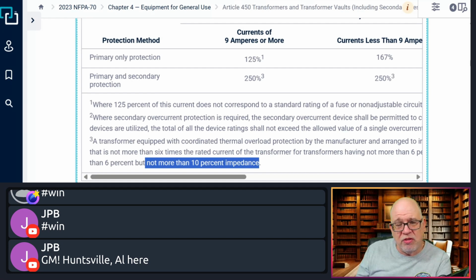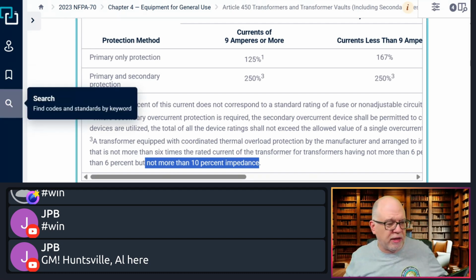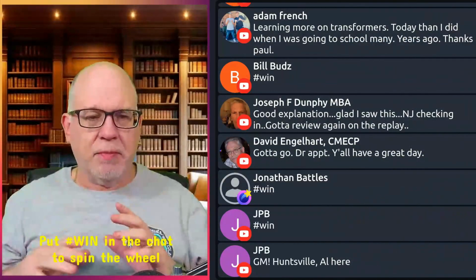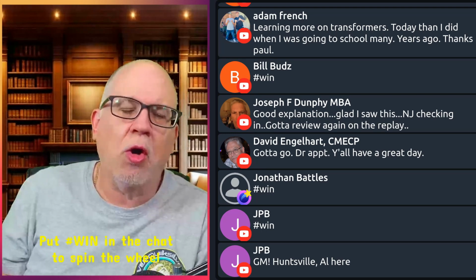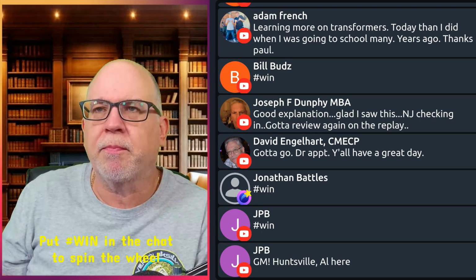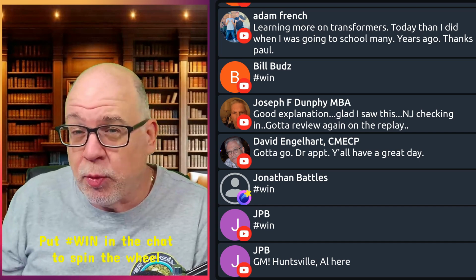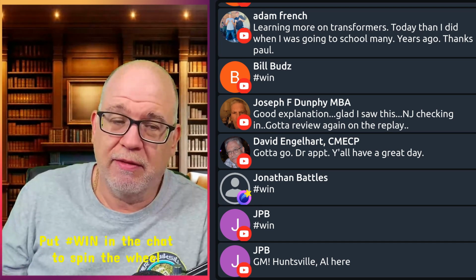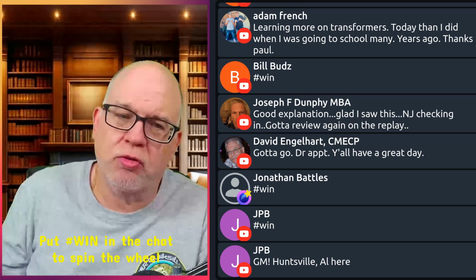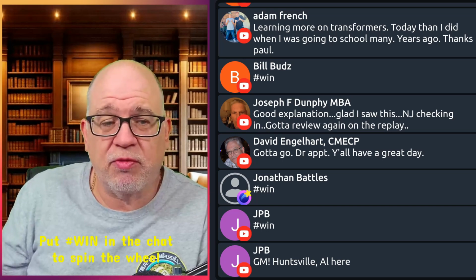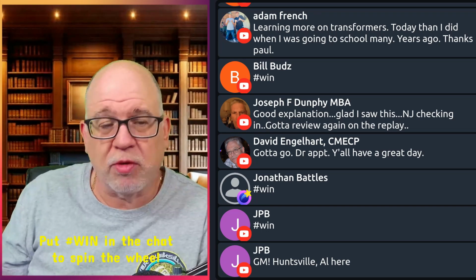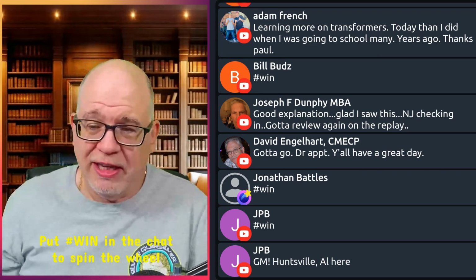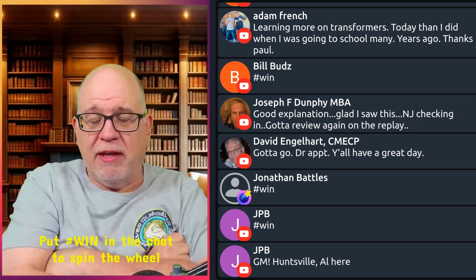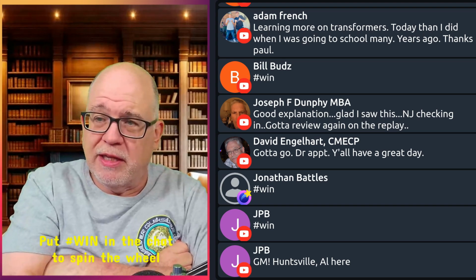So most exams, we just get asked, what's the maximum? If there's a secondary protection, what's the maximum protection on the primary of that transformer? 250%. Now, I'm just talking, but here's something you have to be concerned about and prepared for: if you go up to 250% because you're doing the protection of the transformer, you may not adequately be protecting those conductors on the primary side. Okay? So just because you're going up to 250% because you're allowed to protect the transformer, right? Because that's what we're talking about, you may not have conductors that can handle that. Because in the worst case scenario, if it's continuous loads taking place in this transformer, then you're basically going to do them at 125%.